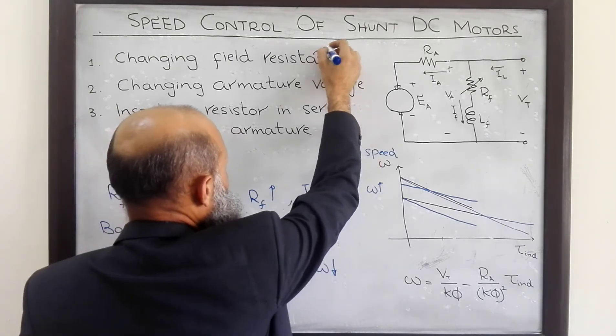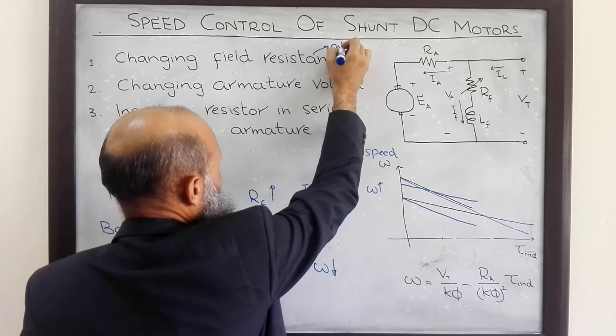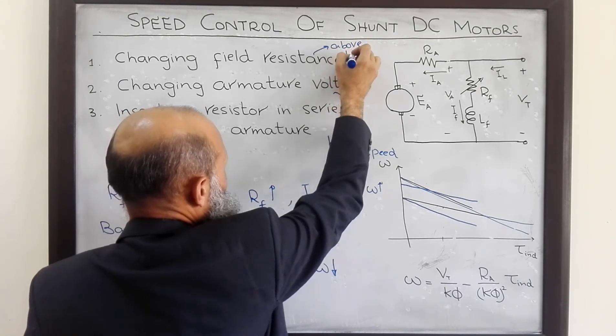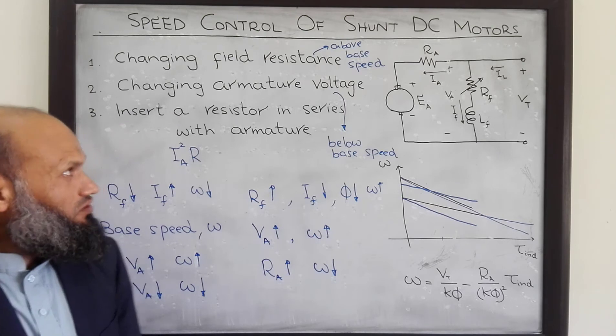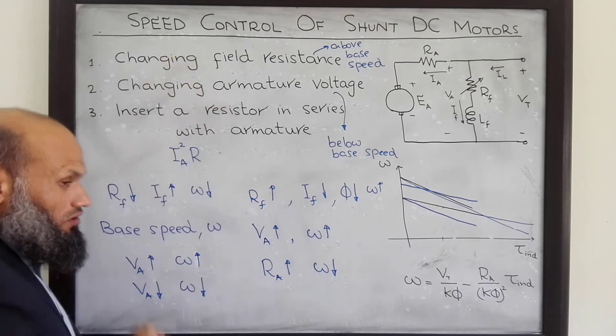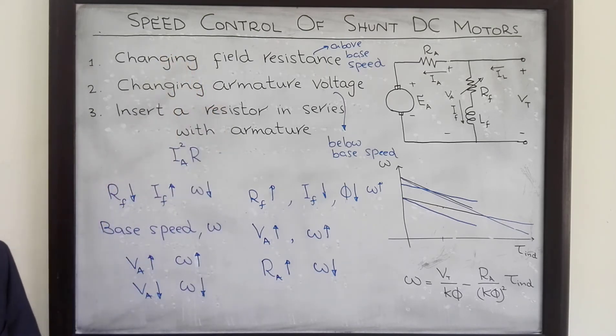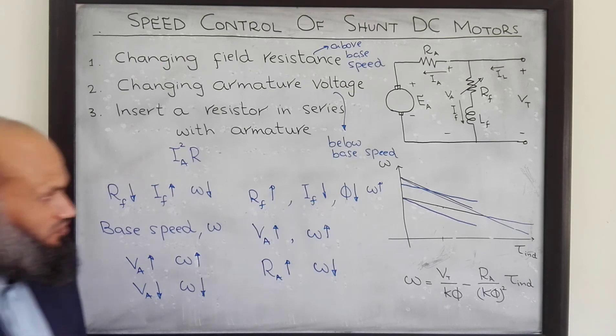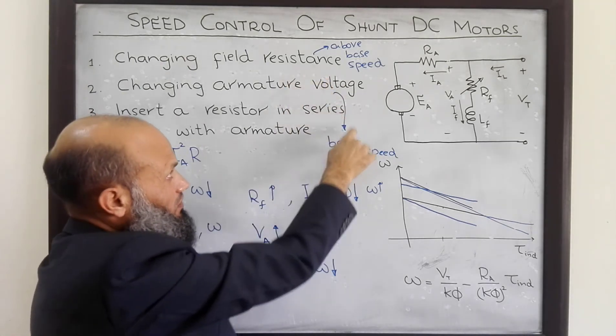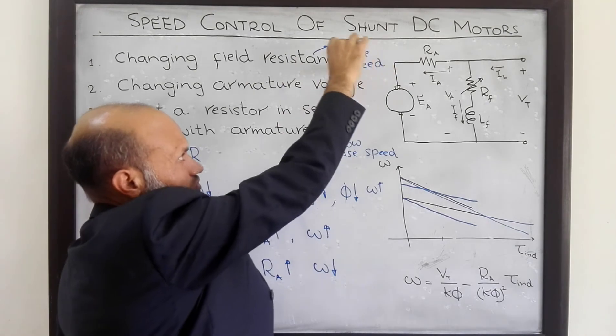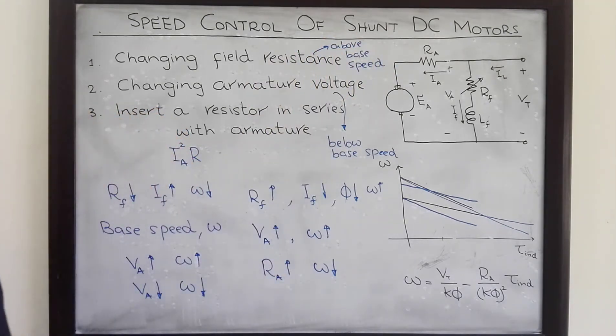In practice, these two approaches are used to complement each other: the armature voltage approach is used to control speed below base speed, and the field resistance approach is used to control speed above base speed.